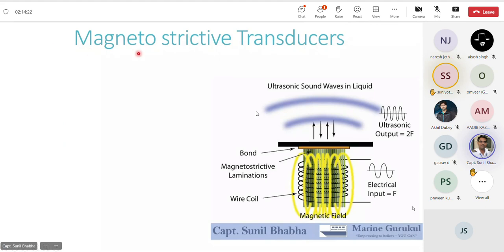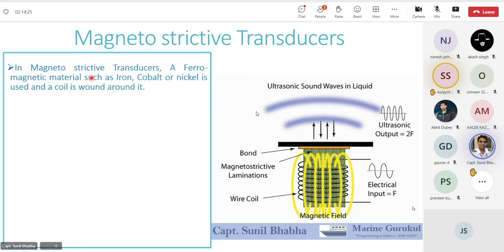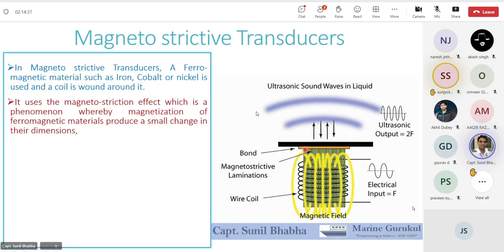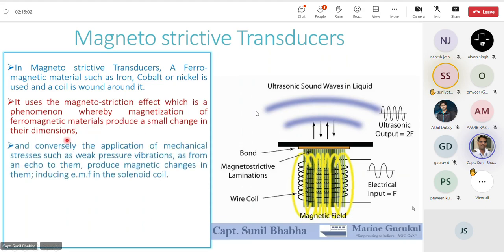Now moving on to a magnetostrictive transducer. In magnetostrictive transducers, a ferromagnetic material such as iron, cobalt or nickel is used, and a coil is wound around it. You can see in the diagram, this vertical line is the material, which is a ferromagnetic material, and you can see there is a coil wound around it, which acts as a solenoid. Now this kind of transducer uses the magnetostriction effect, which is a phenomenon whereby magnetization of the ferromagnetic material produces a small change in its dimensions.